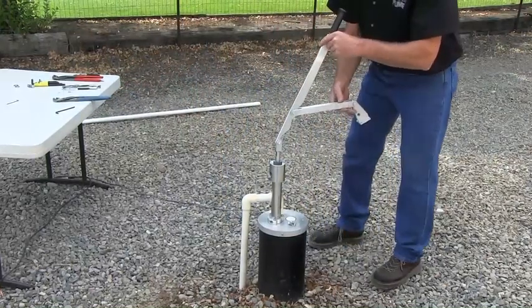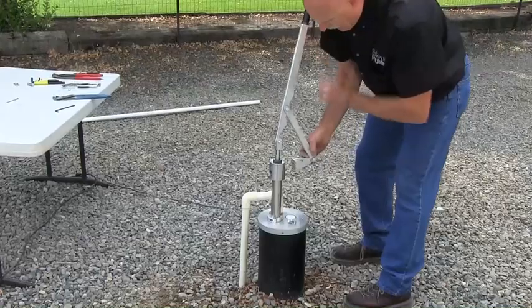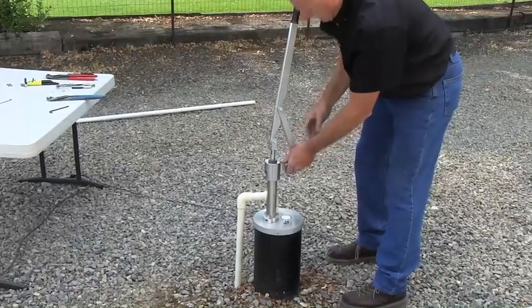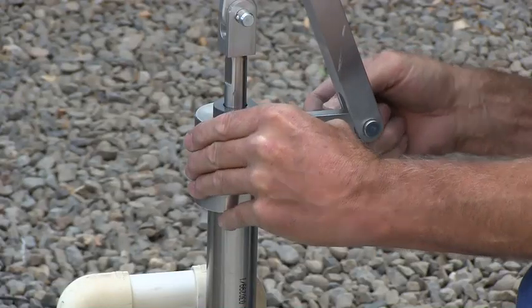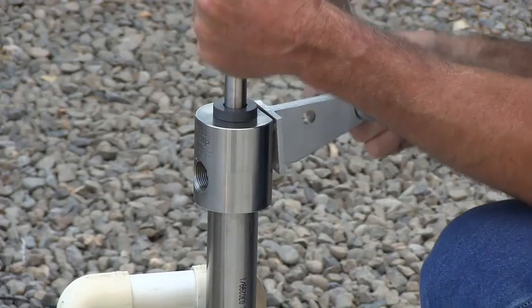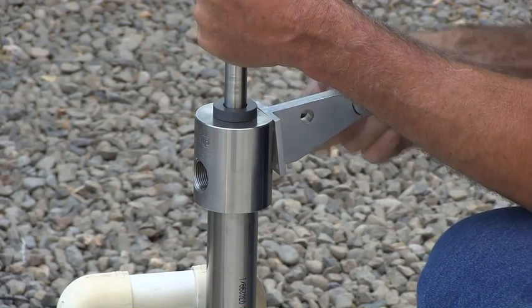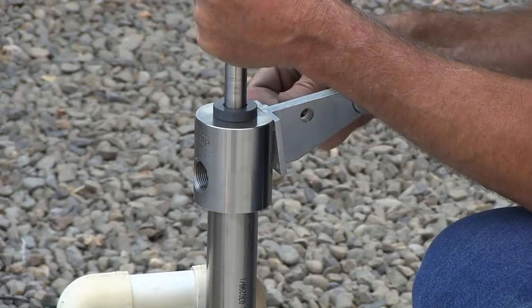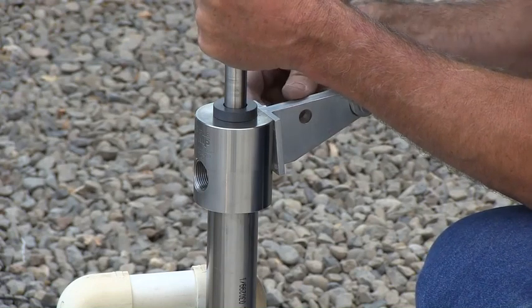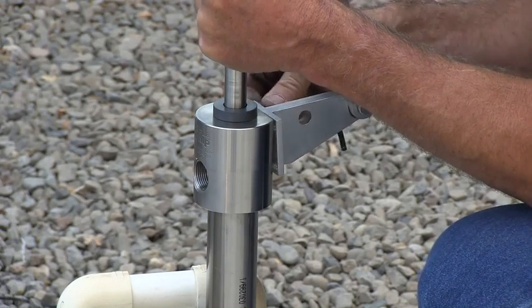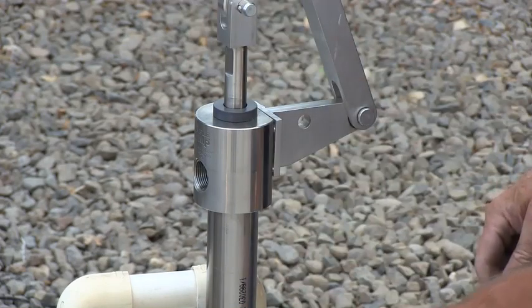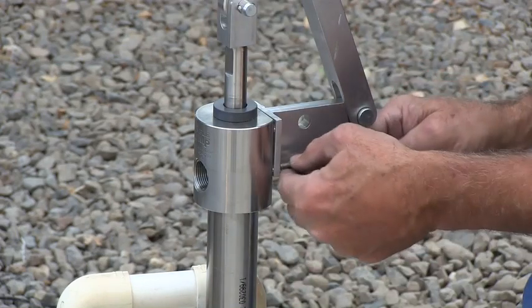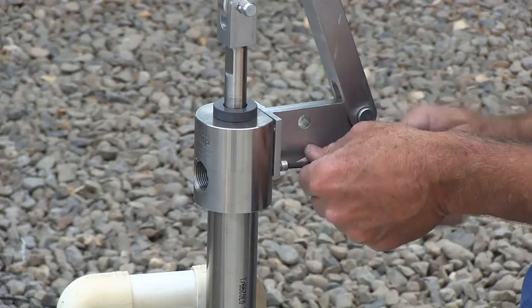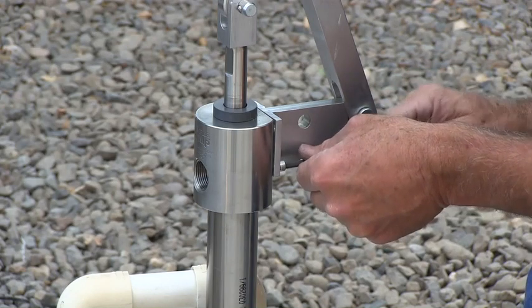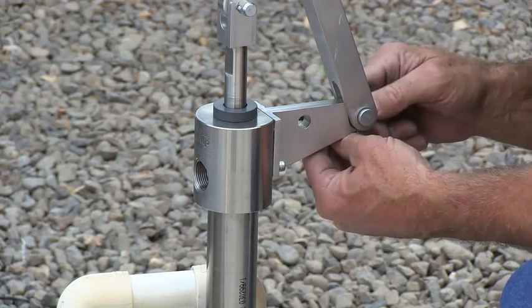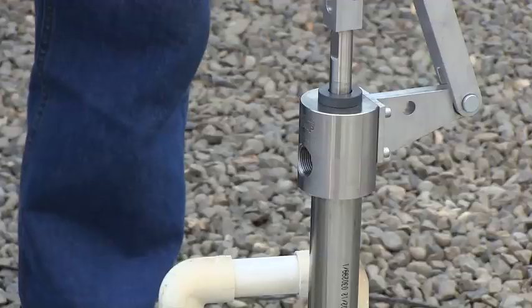Now the lever bracket is brought into position. It may be necessary to lift up on the pump head just slightly to get the holes to align correctly. We got one started here. There are 4 of these 1/4-20, 1/2-inch long stainless cap screws that just need to be snugged up.